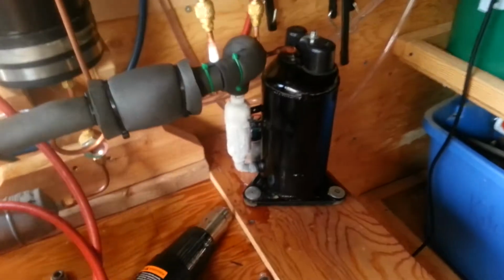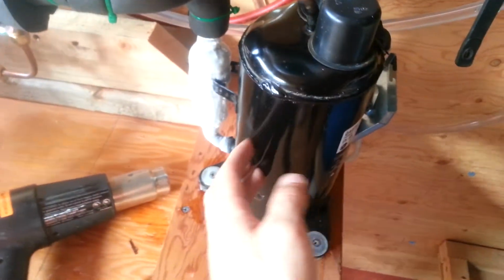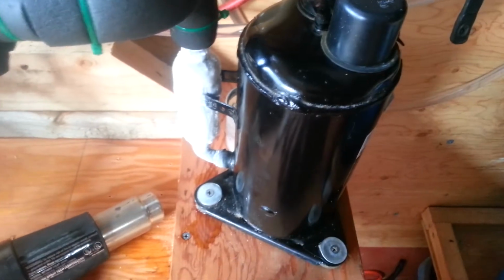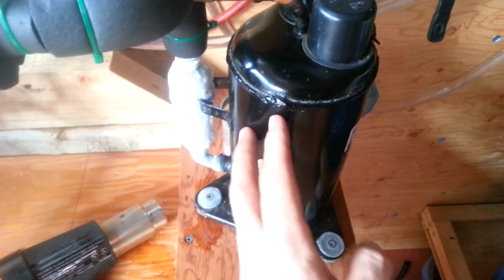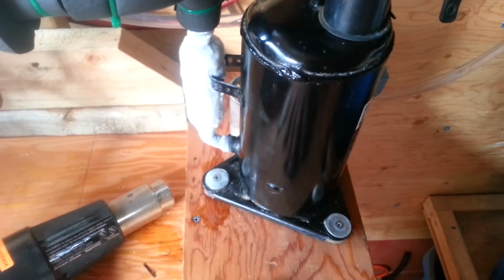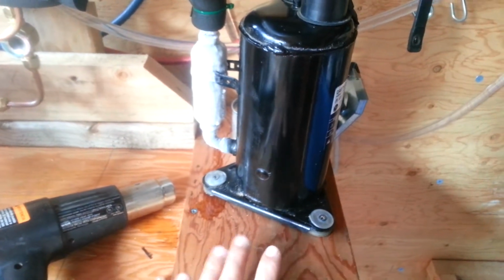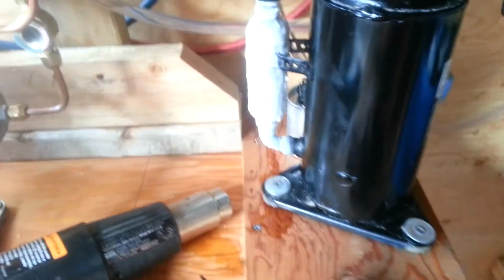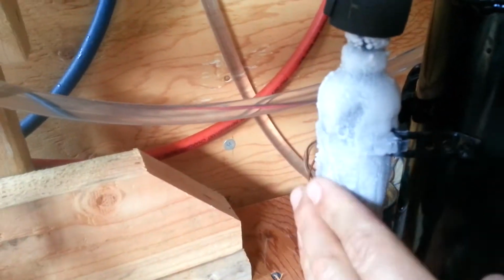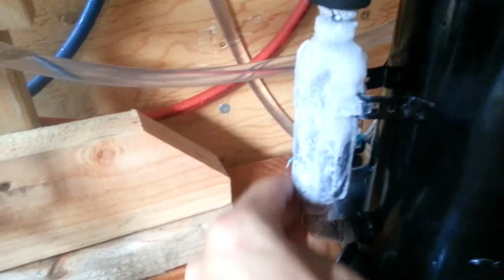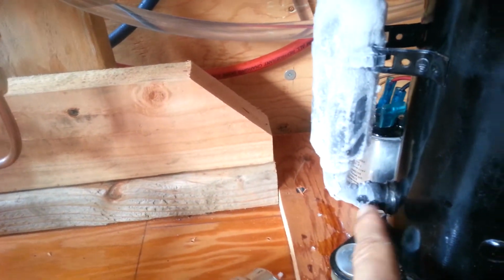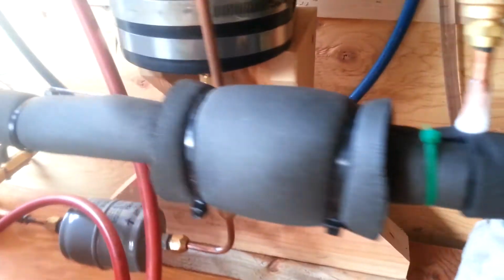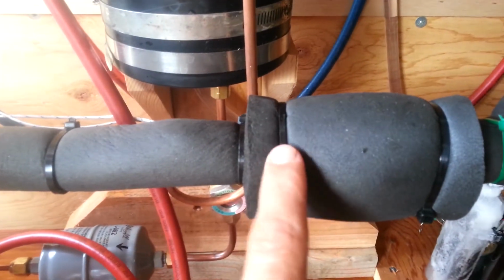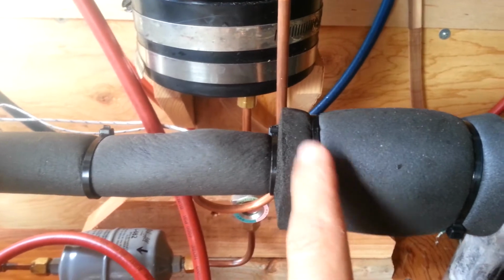If you're watching any of the previous videos, I have a small hermetic compressor out of an air conditioner, a 5,000 BTU per hour air conditioner. It's rotary. I do need to get an amp meter on this thing. I actually have an Energy Detective that I could rig up with this thing on a laptop. So that's going to be really interesting, but I'll probably get into that later this week. You can see the accumulator is pretty frosted up. Frost line never gets past that point there. You can see here where this connection is brazed in for the suction. It's pretty well frosty. This large mass here is about where the suction temperature is taken.